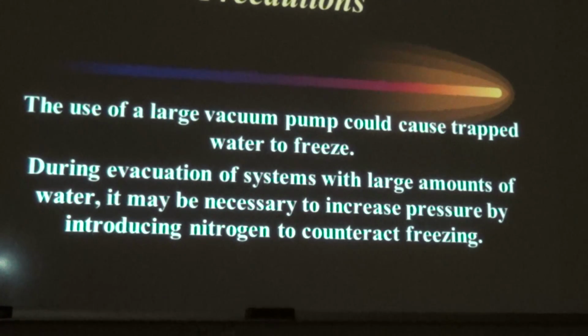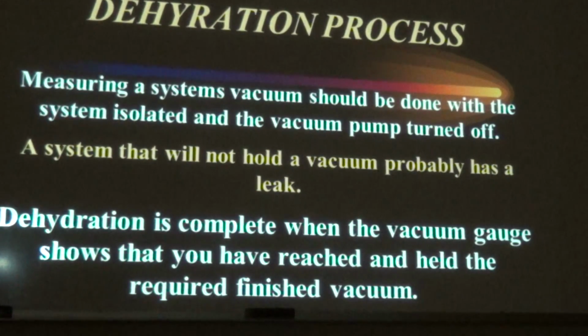Some precautions. If you use a really big vacuum pump, it could cause trapped water to freeze. During evacuation of systems with large amounts of water, it may be necessary to increase pressure by introducing nitrogen from time to time to counteract the freezing. Completing the vacuum process, or completing the dehydration, the removal of the moisture. Measuring a system's vacuum should be done with the system isolated, meaning the manifold gauges are gauged off, and the vacuum pump turned off.